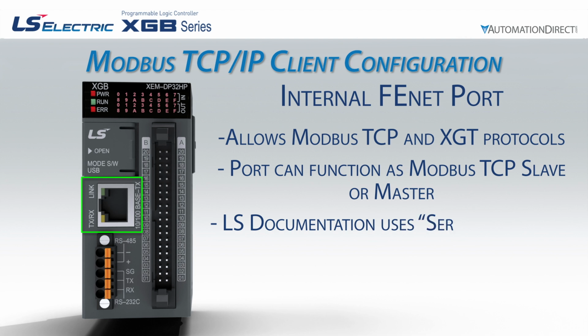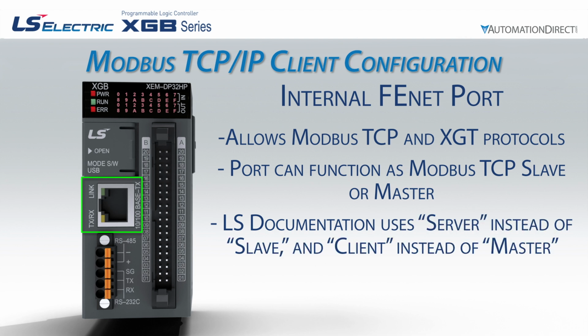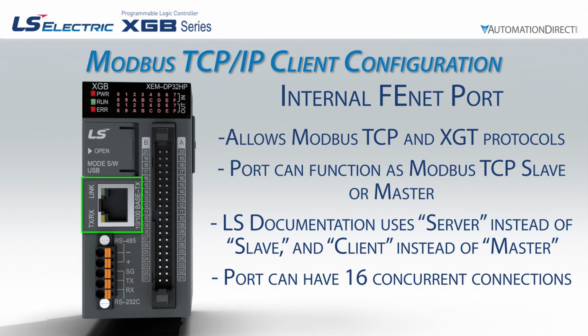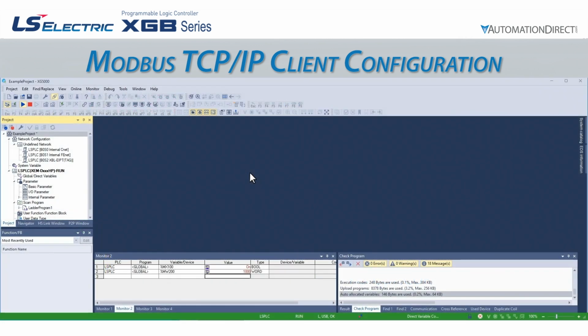In LS documentation, Modbus slave is also called Modbus server, and Modbus master is also called Modbus client. The Modbus server and client functions for the XGB PLC can share up to 16 concurrent connections. Let's set up the XGB PLC as a Modbus client.